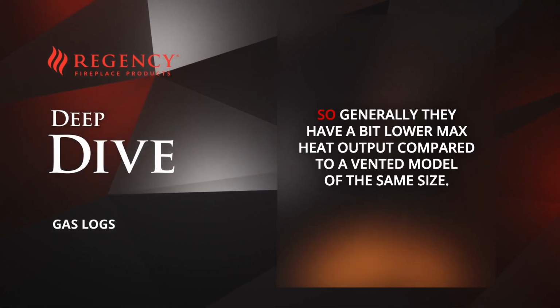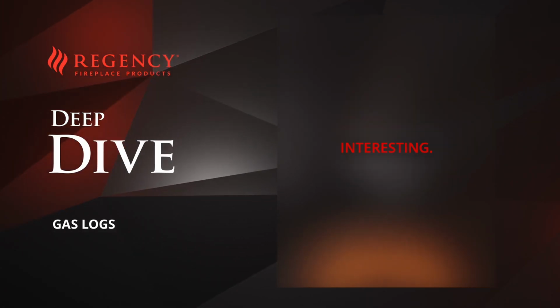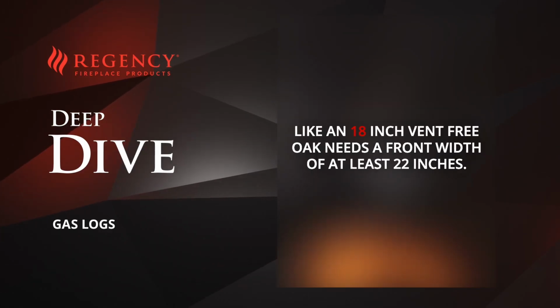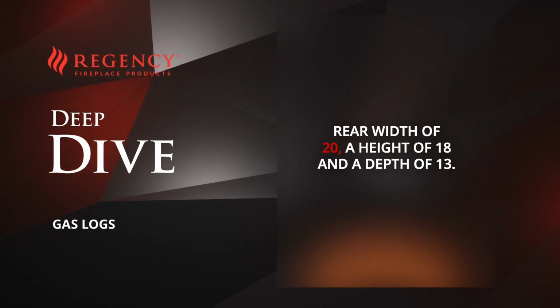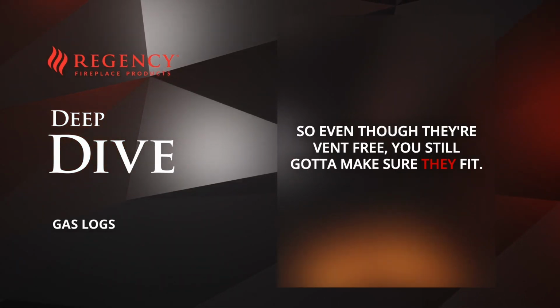Got it. So generally, they have a bit lower max heat output compared to a vented model of the same size. Interesting. And again, just like with vented logs, you absolutely have to check those minimum fireplace opening dimensions for vent-free. Can't stress that enough. Like an 18-inch vent-free oak needs a front width of at least 22 inches, rear width of 20, a height of 18, and a depth of 13. So even though they're vent-free, you still got to make sure they fit.